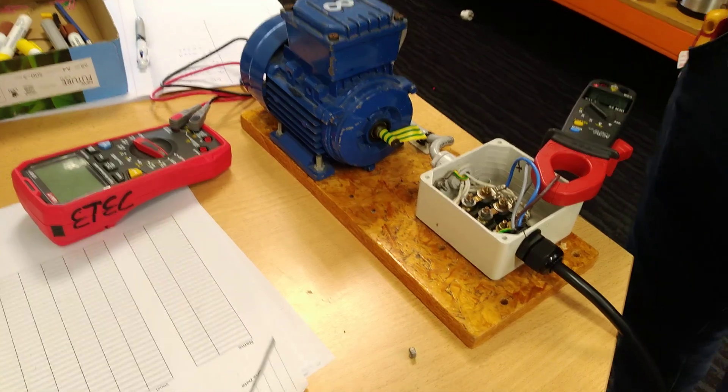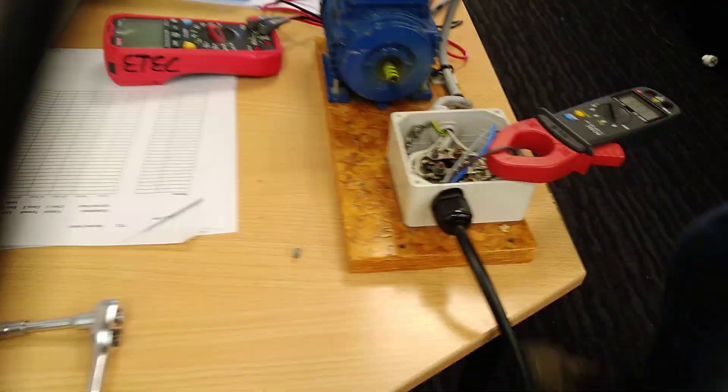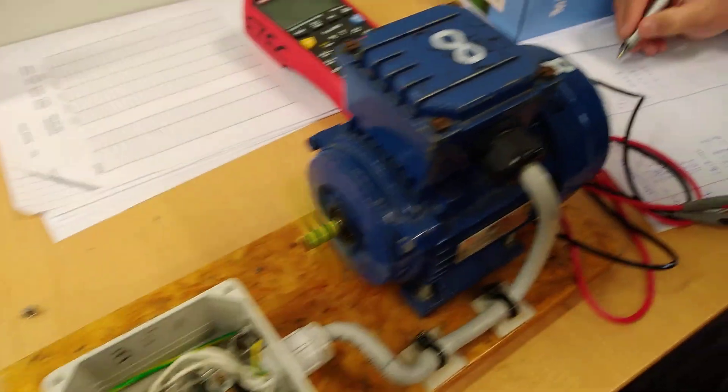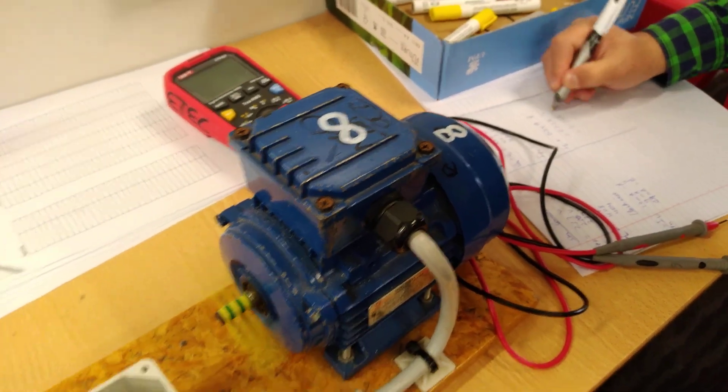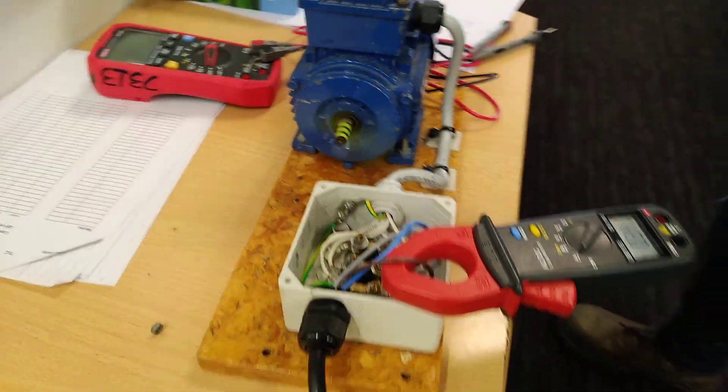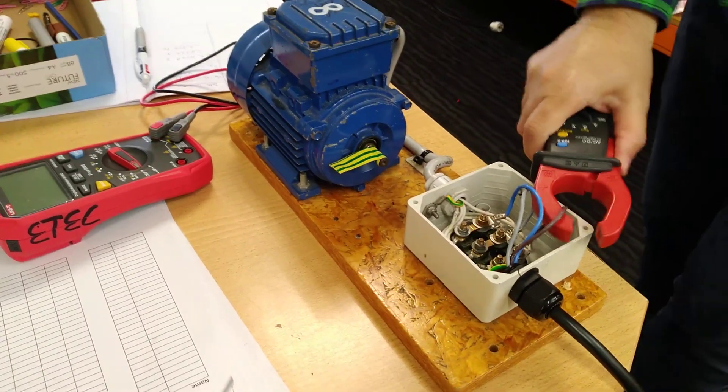And the last one now. Notice the currents are pretty even. So the motor's in good condition. Okay, thank you. So we'll switch off and unplug, and we'll change the direction of rotation.